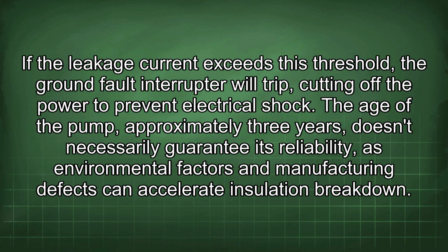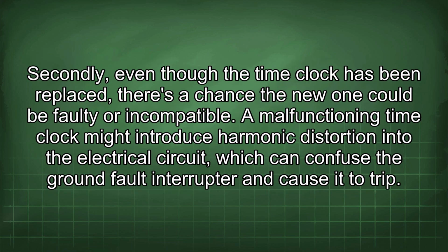If the leakage current exceeds this threshold, the ground fault interrupter will trip, cutting off the power to prevent electrical shock. The age of the pump, approximately 3 years, doesn't necessarily guarantee its reliability, as environmental factors and manufacturing defects can accelerate insulation breakdown. Secondly, even though the time clock has been replaced, there's a chance the new one could be faulty or incompatible. A malfunctioning time clock might introduce harmonic distortion into the electrical circuit, which can confuse the ground fault interrupter and cause it to trip.